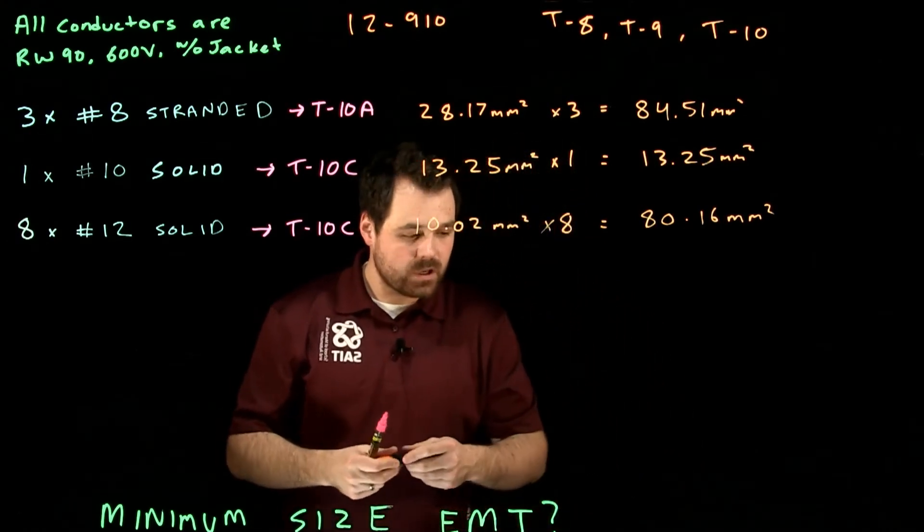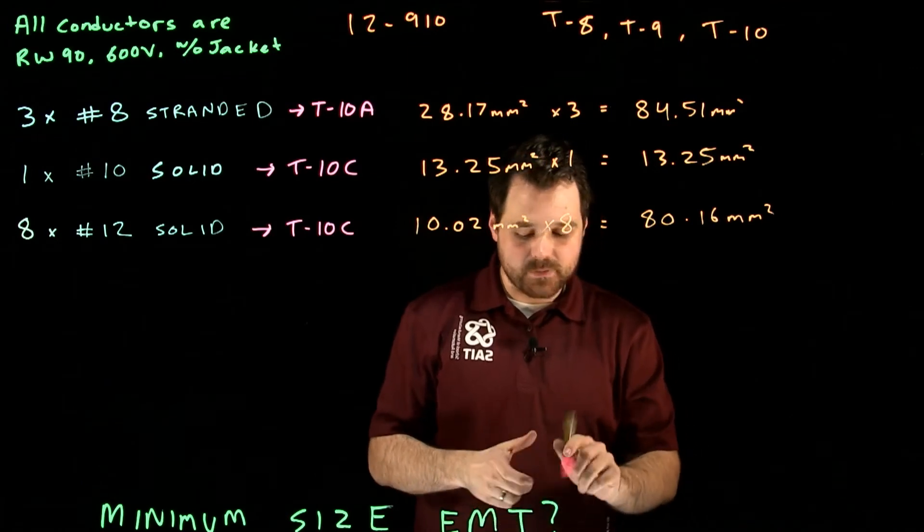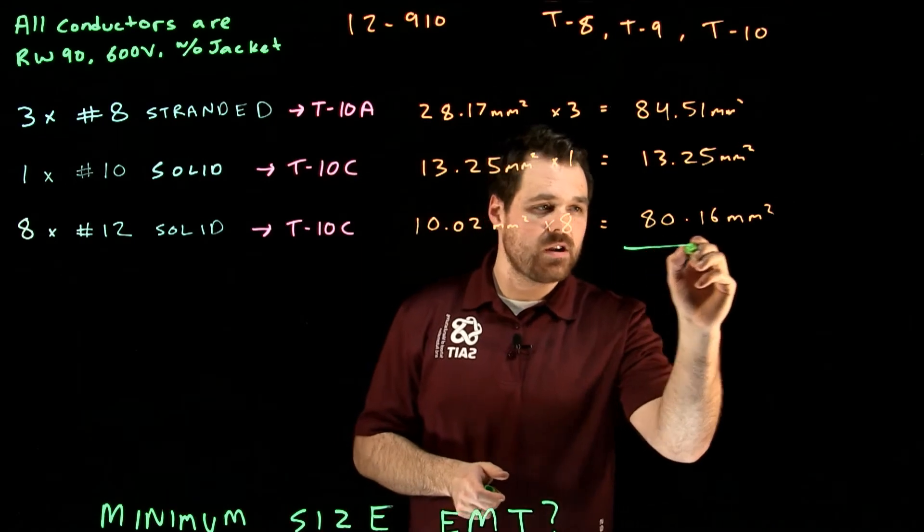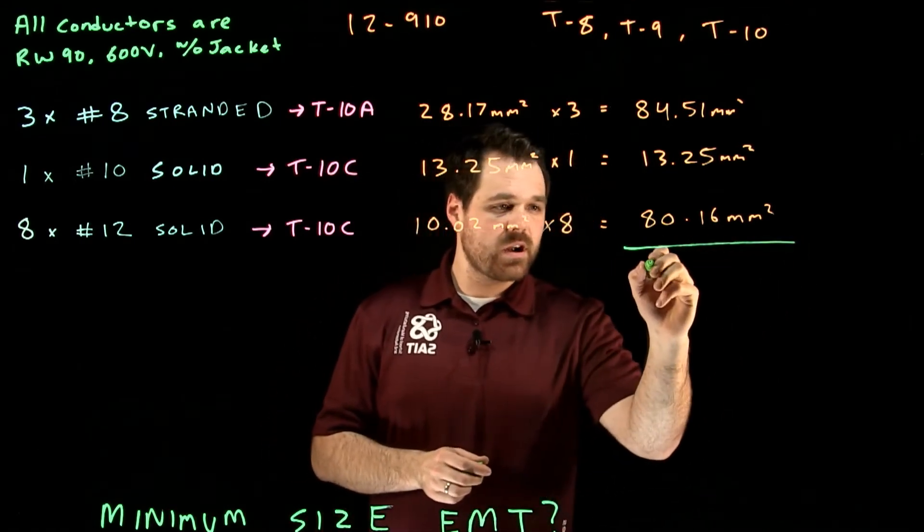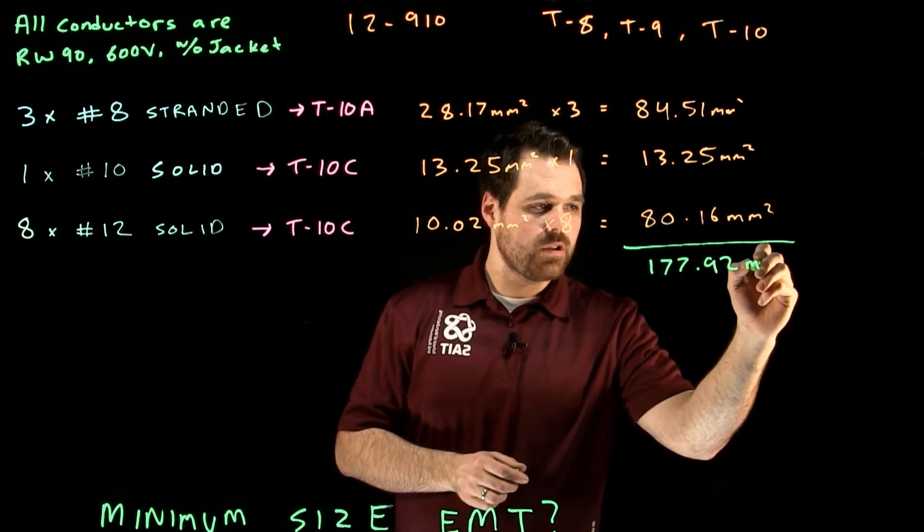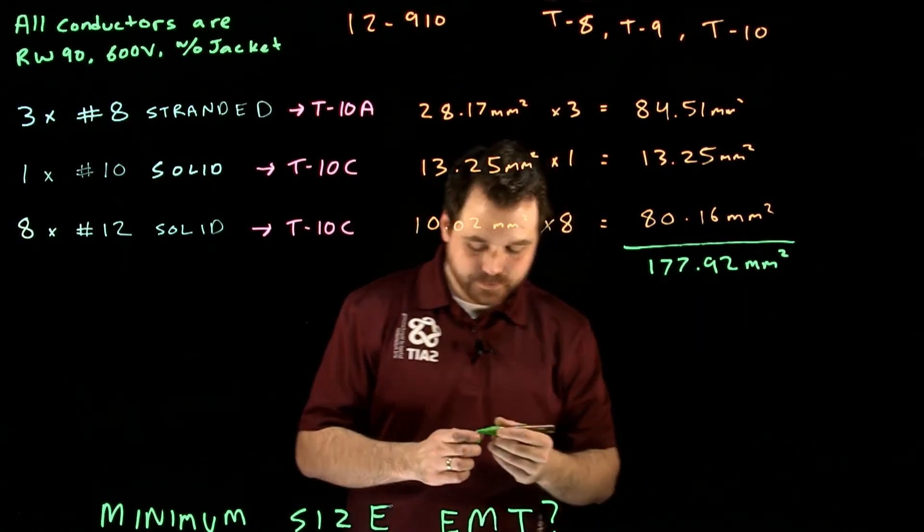Then what we want to do is we want to add all of this up, which is going to give us the total space that these conductors are going to take up in a conduit. So I add all of these numbers up. It gives me 177.92 millimeters squared. Perfect.